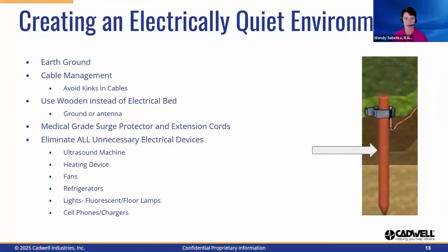The earth ground is a metal rod or pipe that is a minimum of 8 feet long and is buried at least 30 inches deep and below the frost line. According to the National Electric Code, the standard earth ground's resistance should be under 25 ohms.